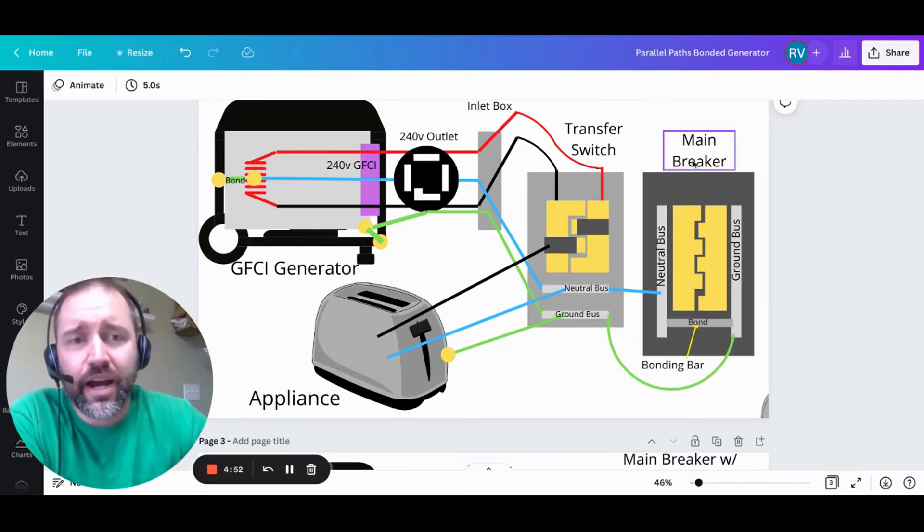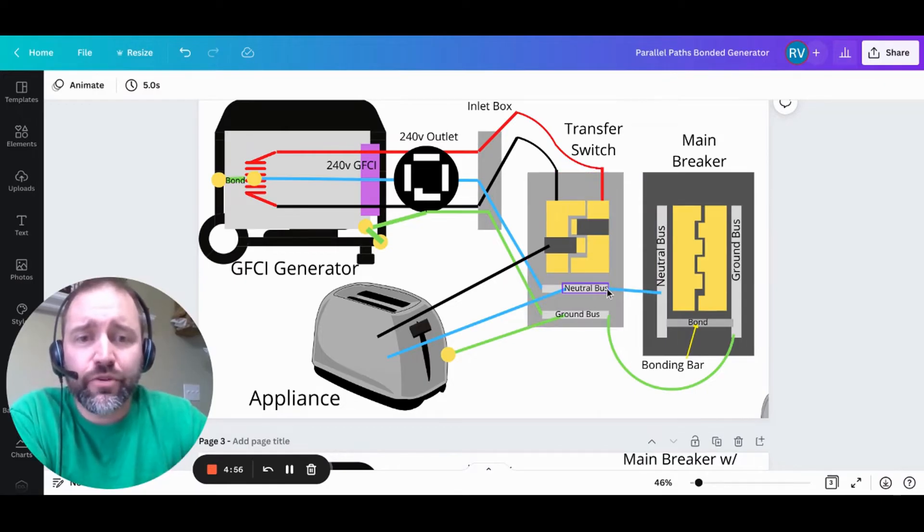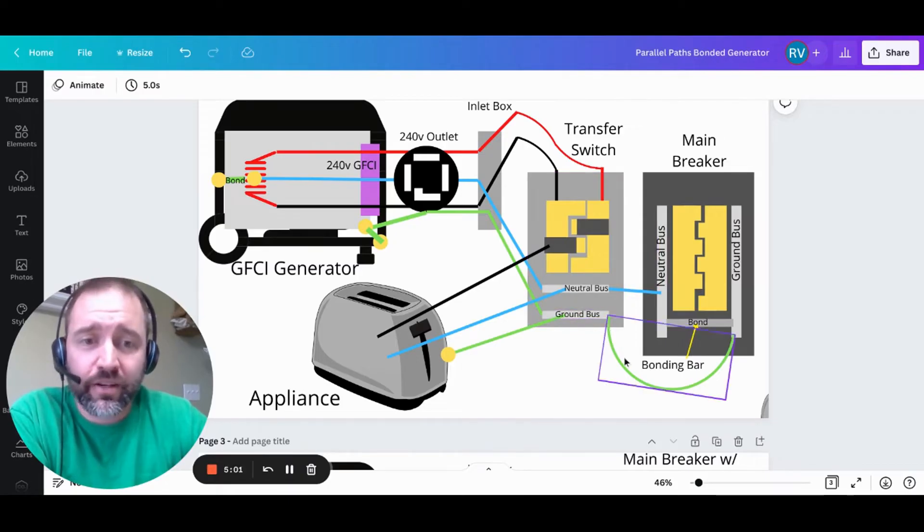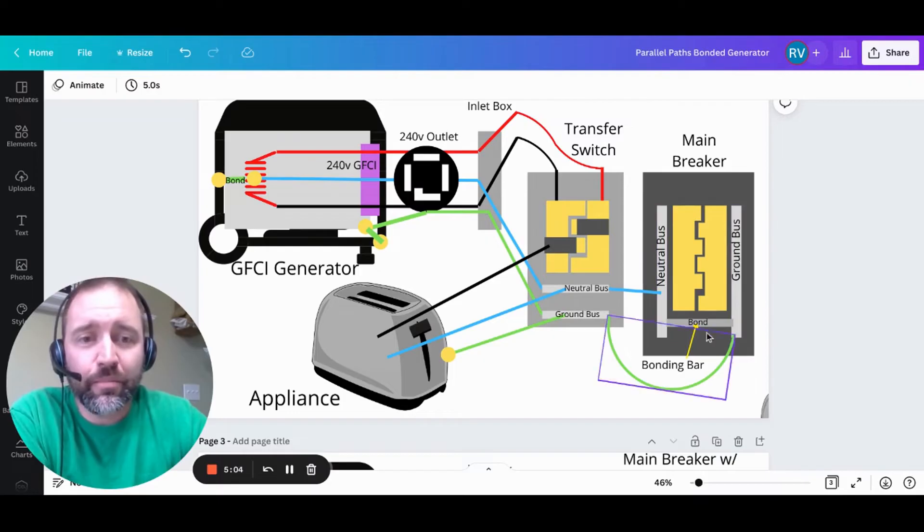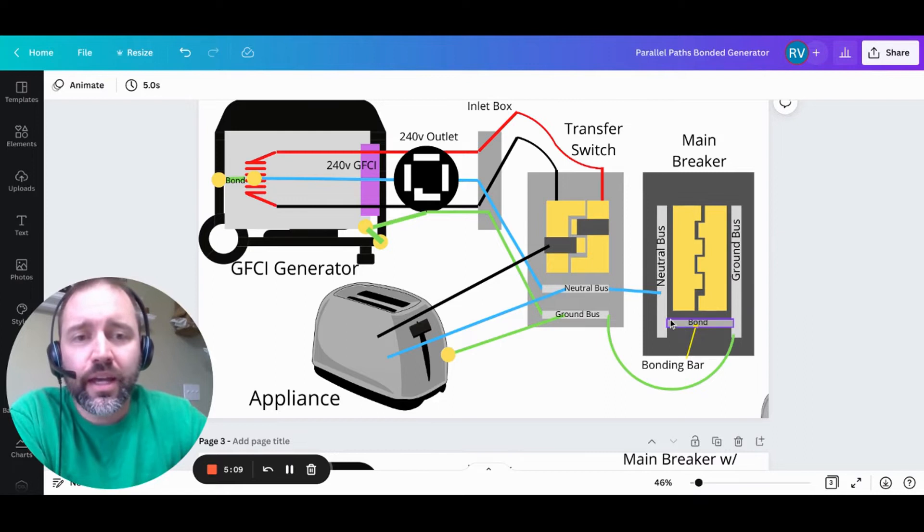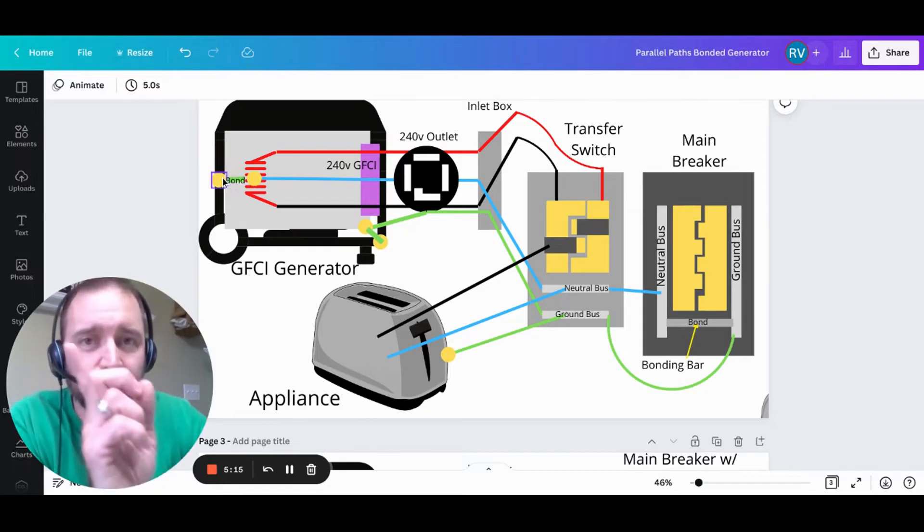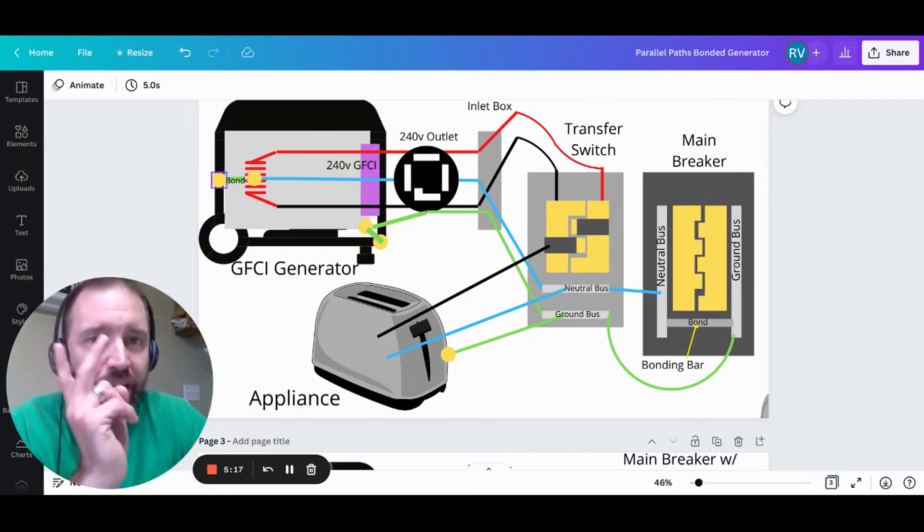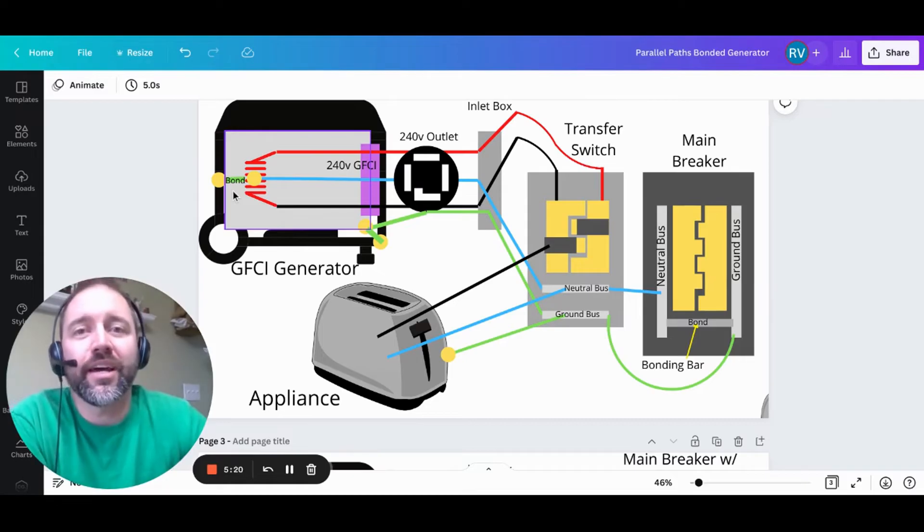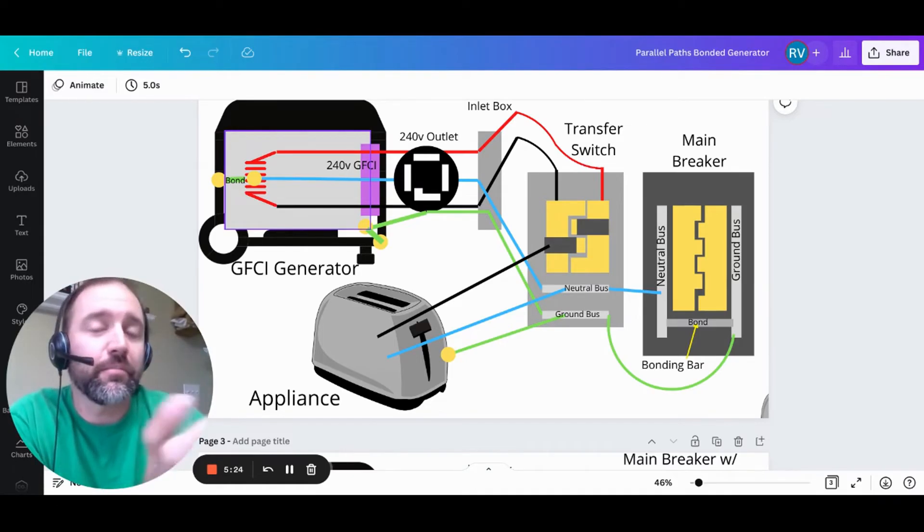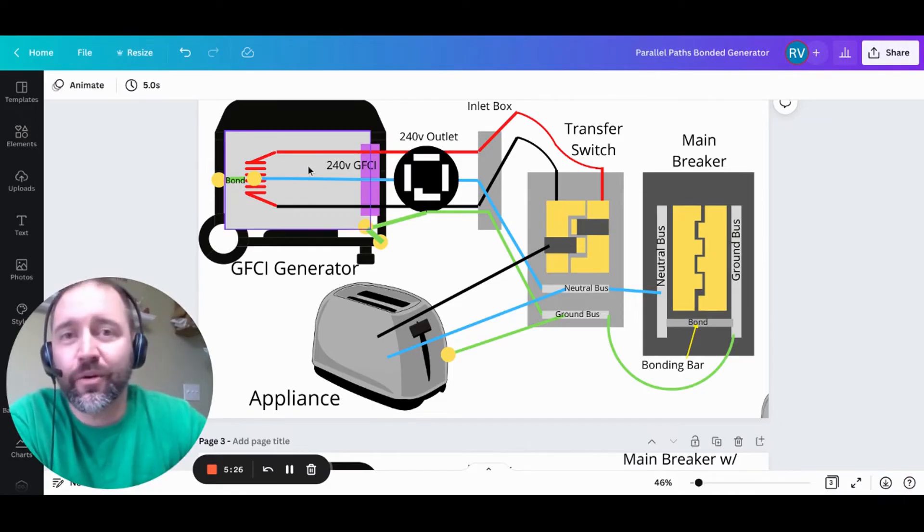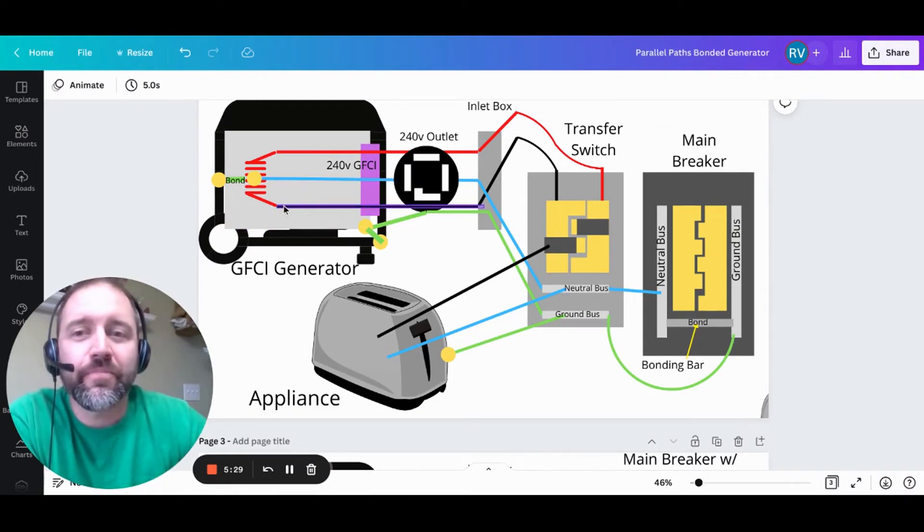Inside of your house at the main breaker, from your transfer switch, you're going to have a neutral wire that runs over to this neutral bus, and then from this ground bus, you're going to have a wire that goes over to this ground bus. Well, inside of the main breaker, there's a bond. It's either going to be a screw or a bar that bonds these two and basically physically links them. So now you have one bond here, and you have one bond here, and in a system, you can only have one. So now that we've presented two, that's where our issue is going to be. It's going to create an alternate or a parallel path back to the source. You'll still complete the circuit, but not everything's going to be going where it should.